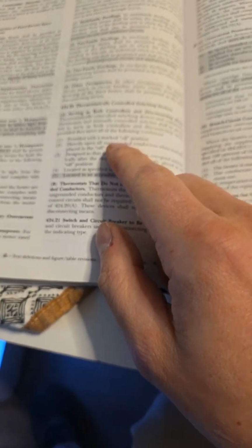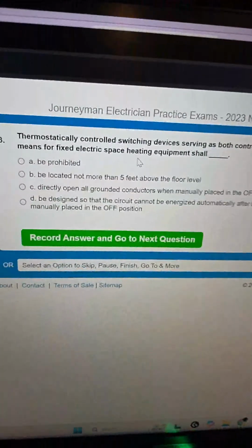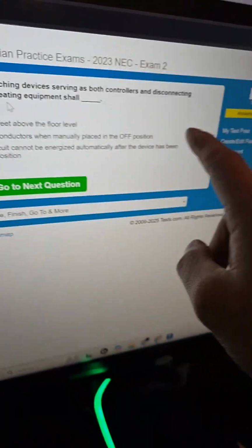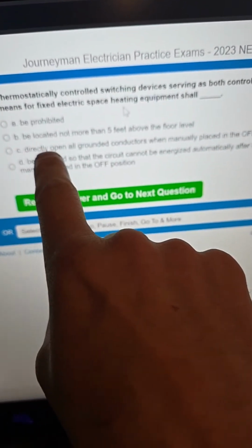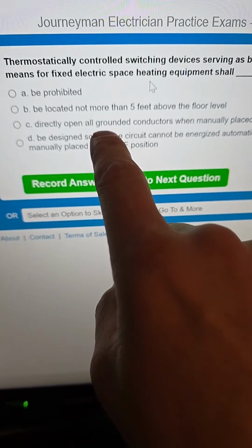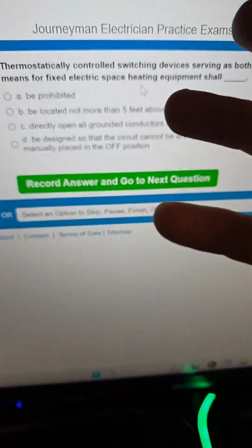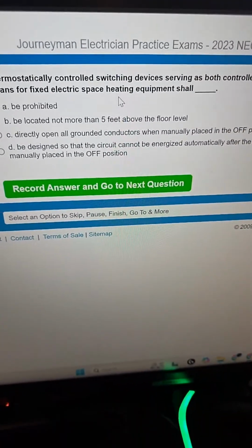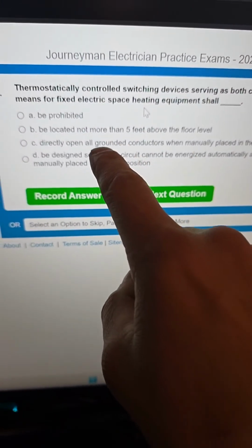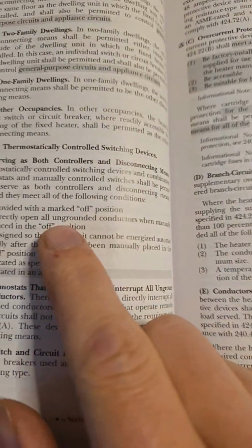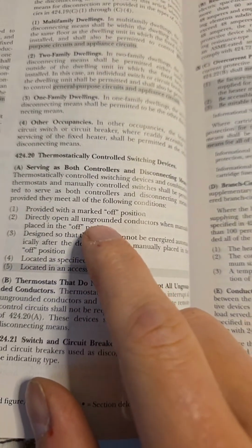Grounded conductors when manually placed directly open all ungrounded. Now check this out. This says grounded, not ungrounded. I'm going to waste some time so you guys can learn here. I've only got 5 minutes anyway. It doesn't matter. Directly open all grounded conductors. Grounded is the neutrals. So grounding is green. Grounded is white. And this is a trick question. Look, grounded. If we look here in the actual question, it says ungrounded here in the code. So this is how they're going to get you.